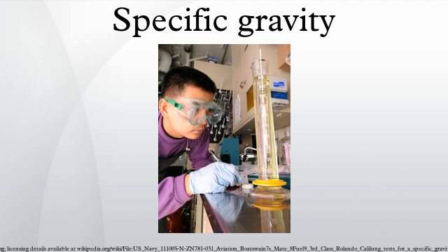Radiation-based gauge: radiation is passed from a source, through the fluid of interest, and into a scintillation detector, or counter. As the fluid density increases, the detected radiation counts will decrease. The source is typically the radioactive isotope cesium-137, with a half-life of about 30 years. A key advantage for this technology is that the instrument is not required to be in contact with the fluid. Typically the source and detector are mounted on the outside of tanks or piping.